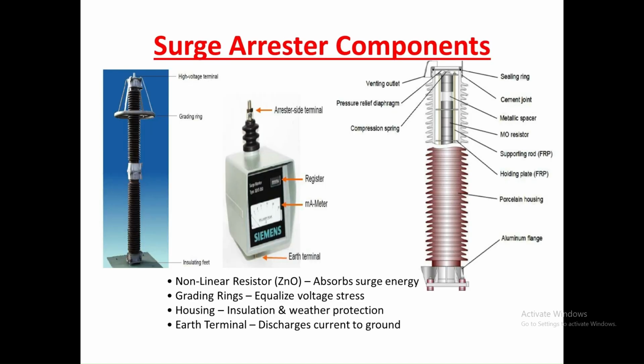Here you can see the picture of a surge arrestor: the high voltage terminal, the grading ring, the insulating feet on the left hand side. In the middle, there is a surge counter which is connected in between the surge terminal and earth, and which reads the number of surges it has encountered, and a milliampere meter is there. And on the right hand side you can see the picture which shows the cross sectional view: porcelain housing, holding plate, supporting rod, MO resistor, cement joint, sealing ring, all the arrow marks that show the venting outlet, pressure relief diaphragm, compression spring, and the functions of each and every individual element.